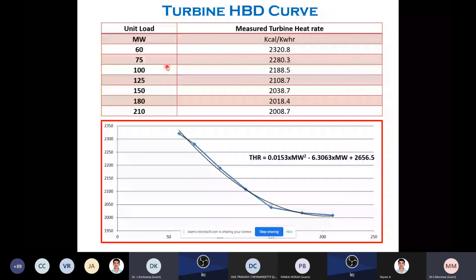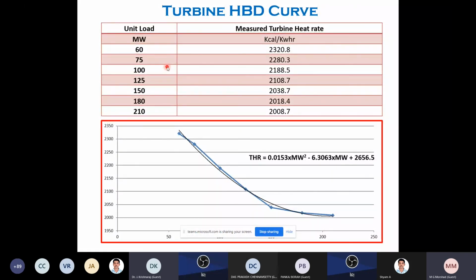I am saying there is a specific power consumption for all the equipment, so you cannot say that it depends only on the load. It depends on the specific power consumption. So at 60 megawatt, this much heat rate, at 75, that much. This data should be provided by the manufacturer. On the basis of that, we have to plot a curve and establish the formula.